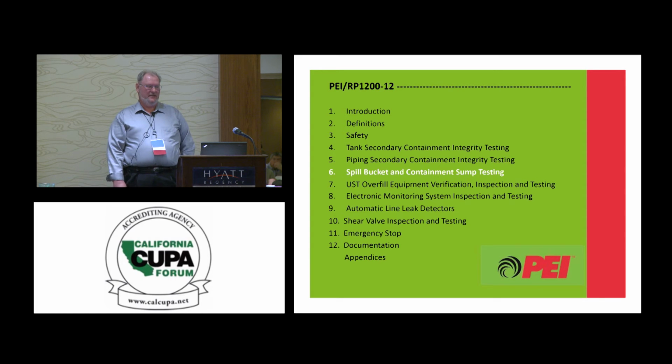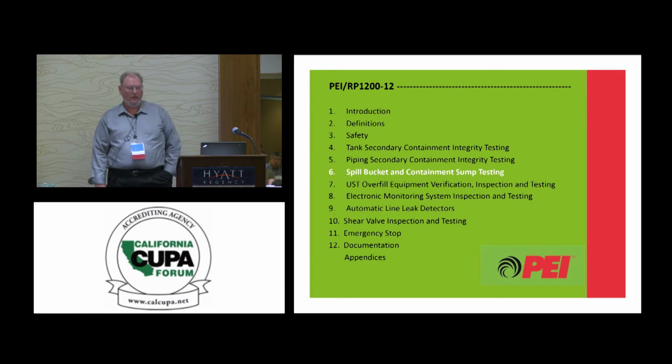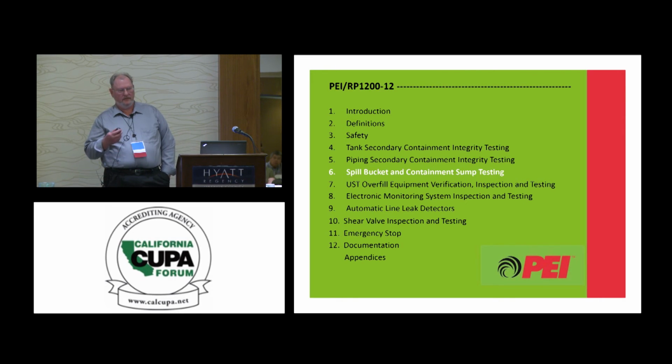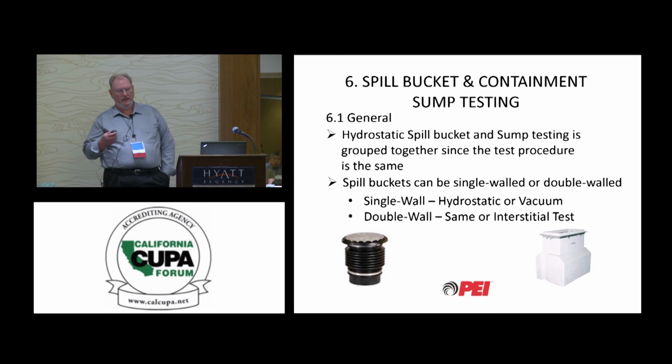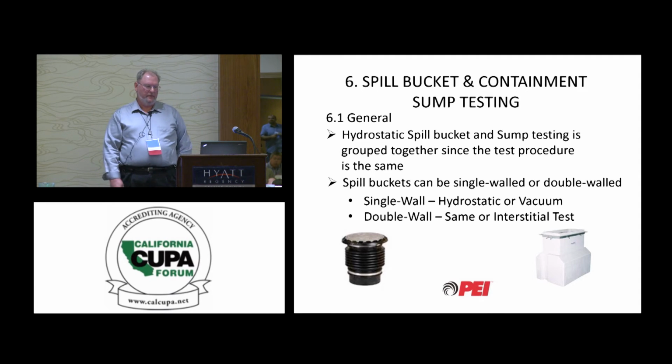Again, the hydrostatic or the spill bucket testing is the same. Or I'm sorry, for double wall spill buckets, you can do a hydrostatic test, a vacuum test, or test the interstitial. We have all three of those procedures in there for a double wall spill bucket.